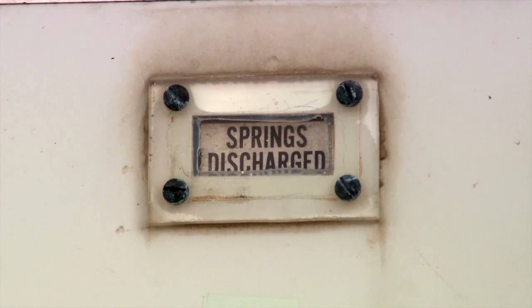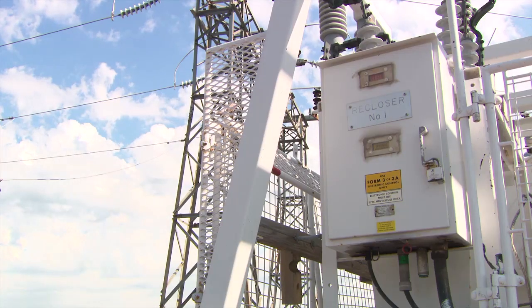This mechanism is supplied with an external trip pull ring that permits manual release of trip springs from beneath the cabinet by hand or with a hook stick. It is also equipped with an external close pull ring that permits manual release of closing springs from beneath the cabinet by hand or with a hook stick.